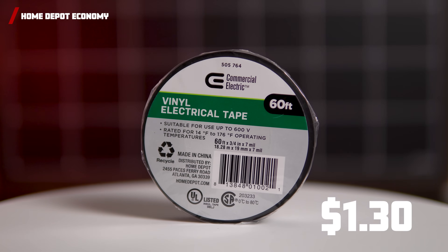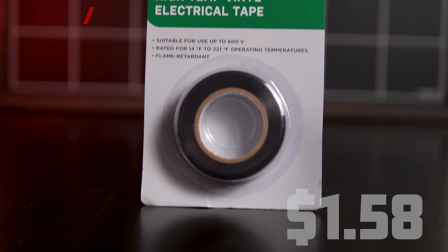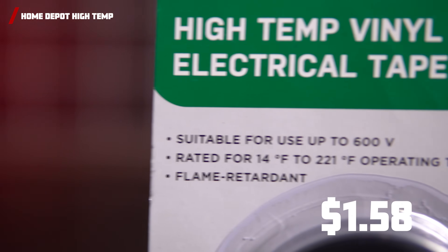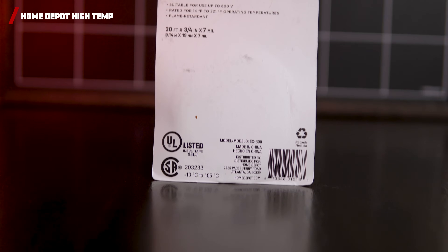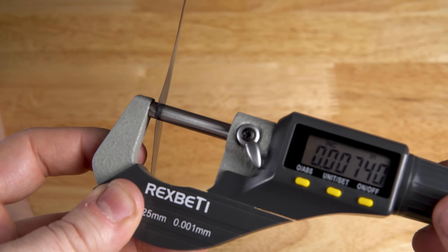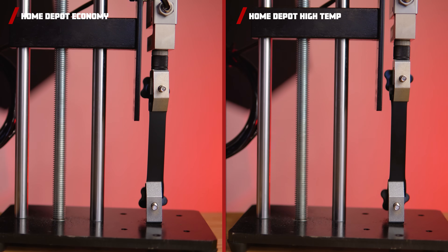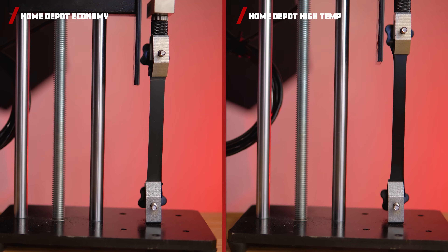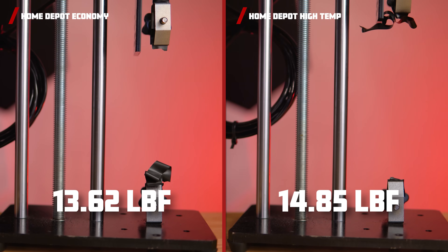At a price of $1.30, we have Home Depot's Commercial Electric Economy, and at $1.58, the high-temperature vinyl tape. The Economy is rated at 176 degrees, and the High Temp is rated at 221 degrees Fahrenheit. Although the High Temp is advertised as 7 mils thick, it actually measures 7.4 mils. These tapes are really strong, with average tensile strengths of 13.62 and 14.85 pounds of force.